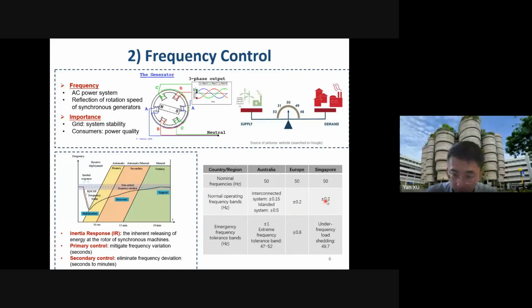For example, in Singapore, for normal operating conditions, we can allow plus minus 0.2 hertz frequency deviation. Then in Europe, the same. In Australia, it's more stringent. For an interconnected system, they can only allow plus minus 0.15. But for an islanded system, they are quite generous, 0.5 hertz plus minus. So that is for normal operation. If we just randomly turn on and off our power demand, then we can tolerate such a frequency deviation.